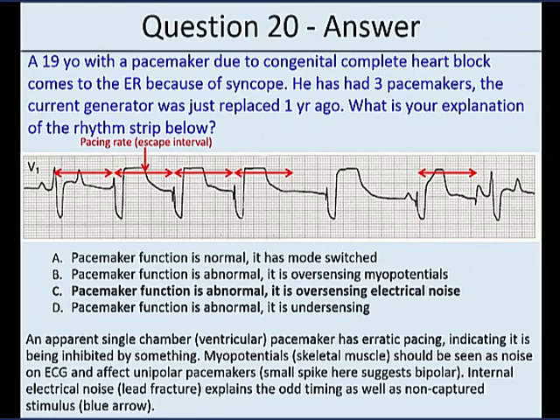So on here, I should also say that myopotentials that are from skeletal muscle occur in everybody. You're doing vacuuming or sweeping or something like that, a lot of myopotentials. Pacemakers see signals like that on a couple of occasions. One is if it's a unipolar sensing pacemaker. Don't use those too much nowadays. That is where to do anything, to either record a signal or pace, you have to have two poles. So what is a unipolar? Well, it's a very wide two-pole. You got a pole on the ventricular end of things with a ventricular pacemaker, and the other pole is the can of the device itself.